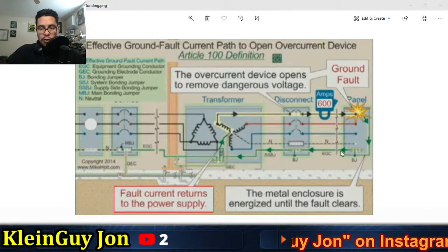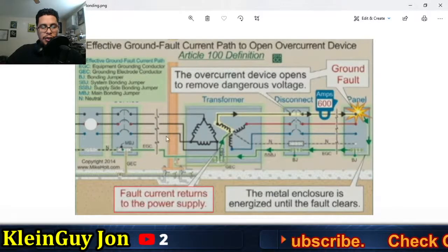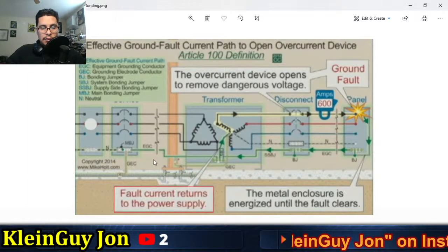You have a fault, electrons are going through all the metal, right? They're going through everywhere until it ends up at the grounding electrode conductor. It will go into the ground electrode conductor, into the earth, and if somebody was standing right here, leaning on the steel or touching anything metallic in the building, you've got electrons going all over the place. Someone's going to get shocked or electrocuted and killed, because now you have all these parallel paths, including the earth. That's dangerous. Now, if you don't have, I'm sorry, let me take that back. Let's say you don't have this bonded.